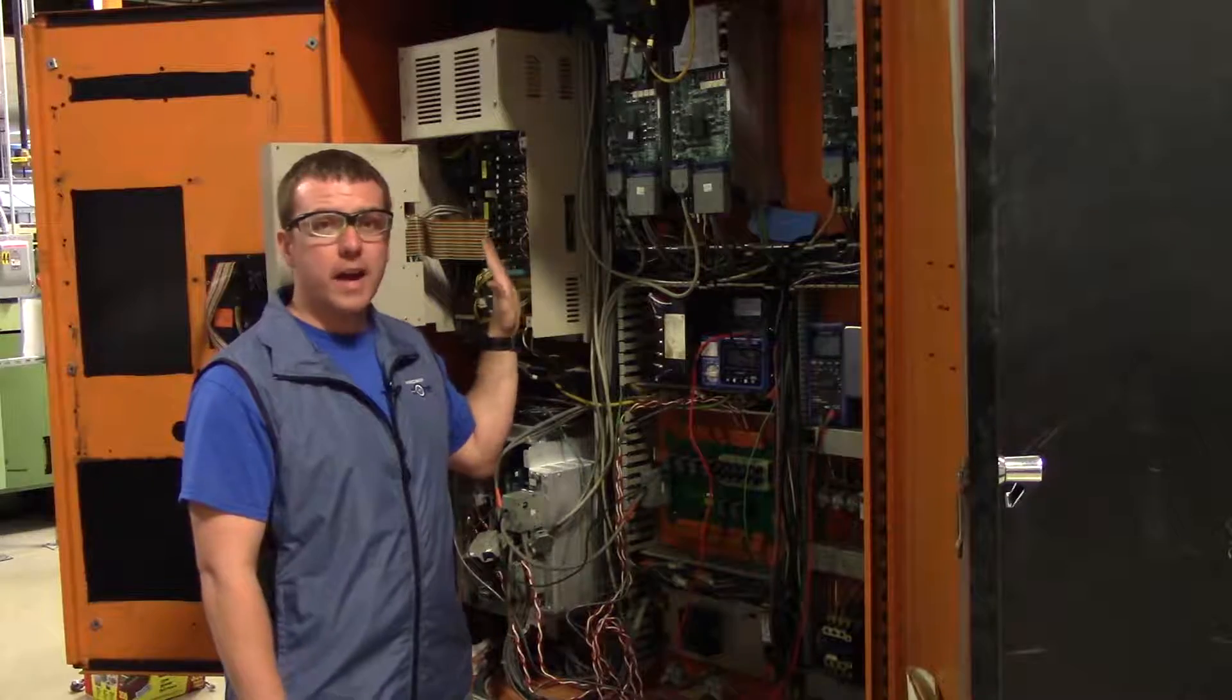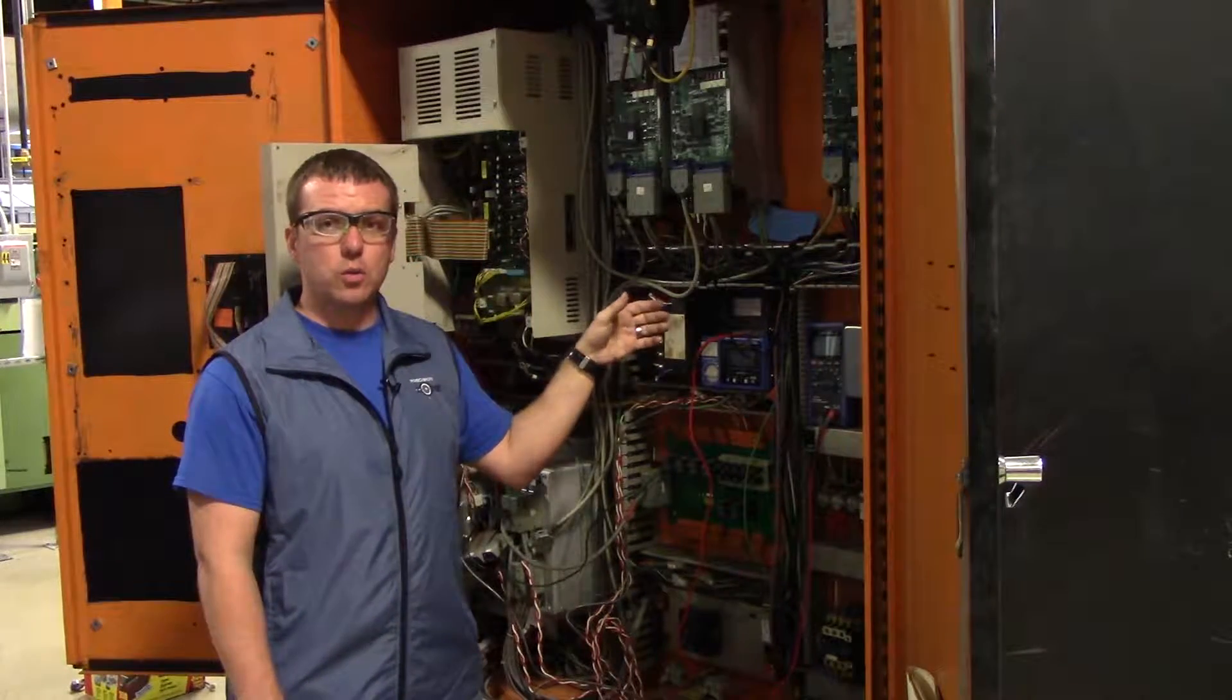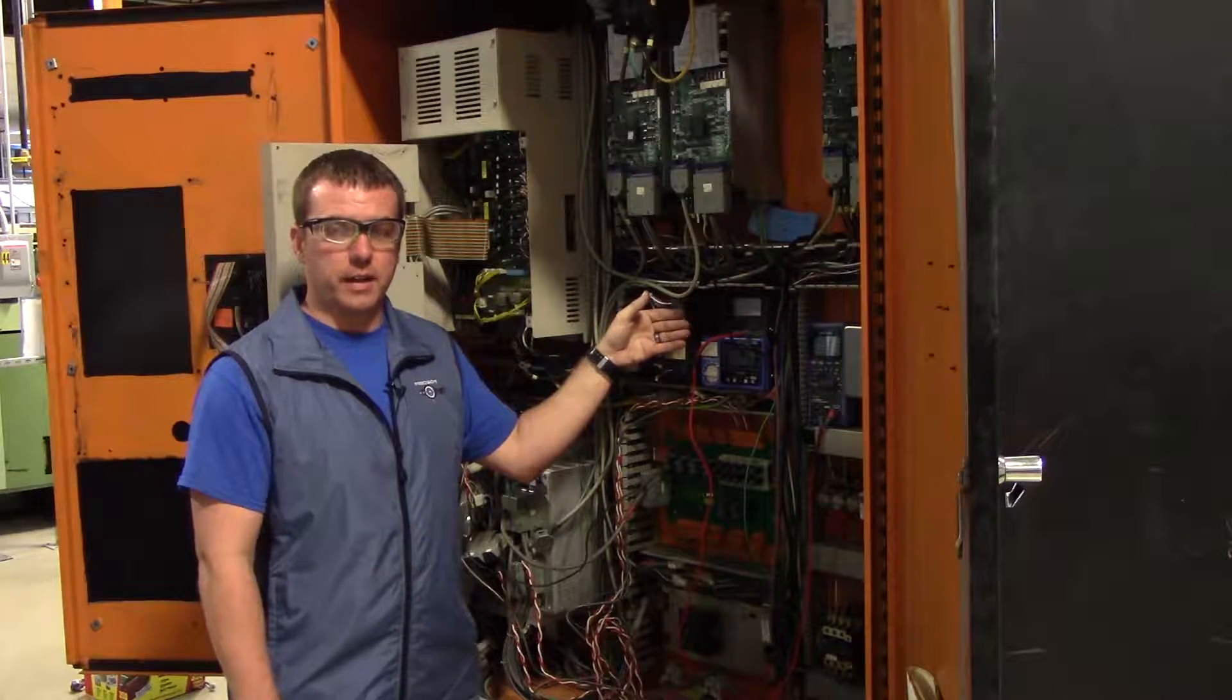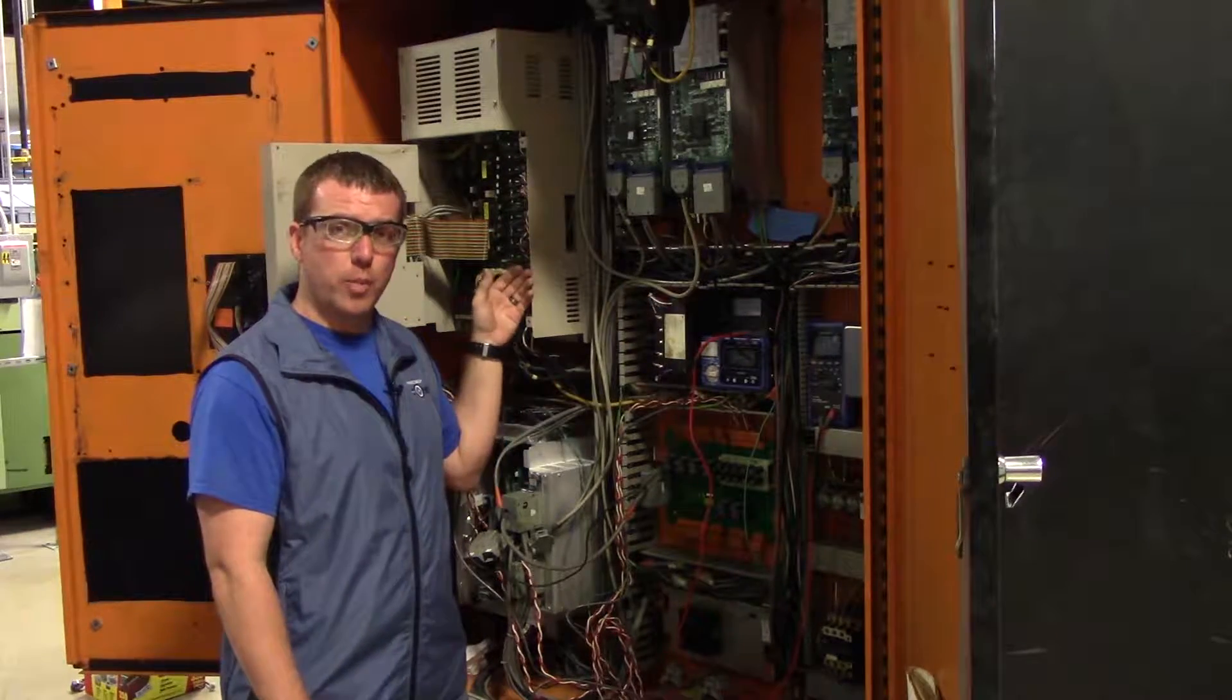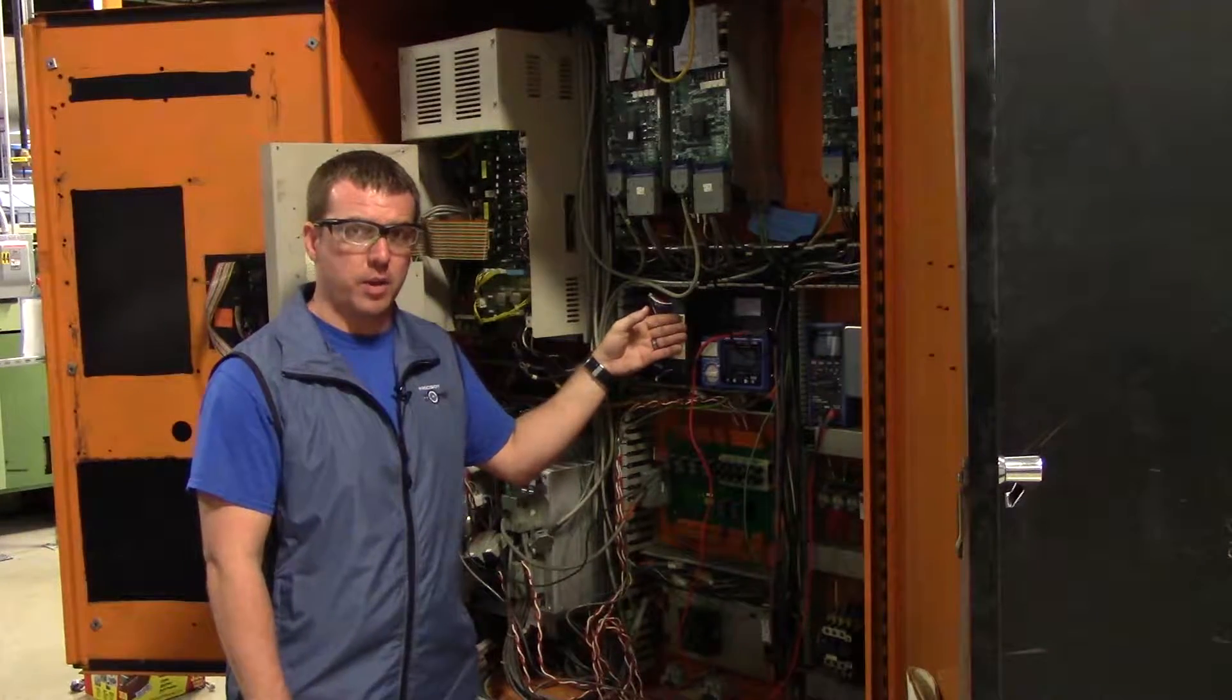Now if you've had a spindle drive in for repair, we always recommend that you change this contactor. Compared to the price of a repair on the drive, it's just cheap insurance to make sure this wasn't damaged.